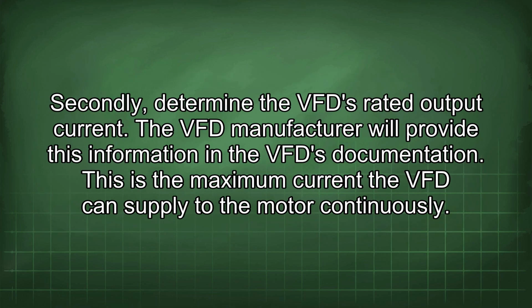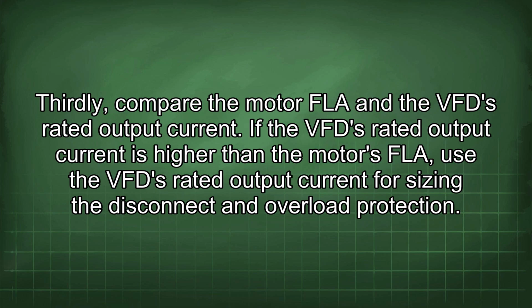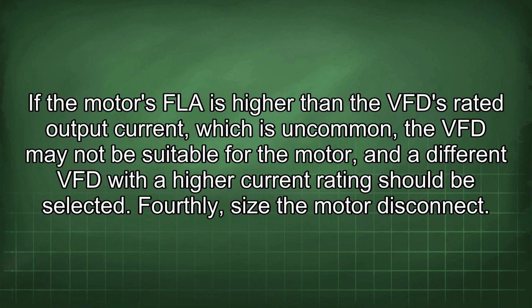Secondly, determine the VFD rated output current. The VFD manufacturer will provide this information in the VFD documentation. This is the maximum current the VFD can supply to the motor continuously. Thirdly, compare the motor FLA and the VFD rated output current. If the VFD rated output current is higher than the motor's FLA, use the VFD rated output current for sizing the disconnect and overload protection. If the motor's FLA is higher than the VFD rated output current, which is uncommon, the VFD may not be suitable for the motor, and a different VFD with a higher current rating should be selected.